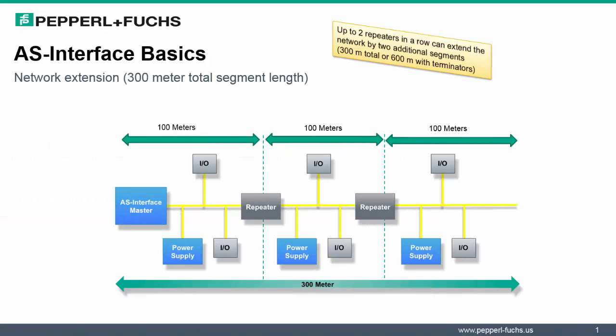Let's consider networks longer than 100 meters in length. Network extension is possible with AS Interface by the use of repeaters and terminators. Up to two repeaters in a row can extend the network by two additional segments. In the diagram here, we have our ASI master at the leftmost position. We have the ability to extend the network up to 300 meters by the use of two repeaters. But again, our restriction is that only two repeaters can be added to the right of our master. Thus, what we accomplish is now our network increases from 100 meters to 300 meters.